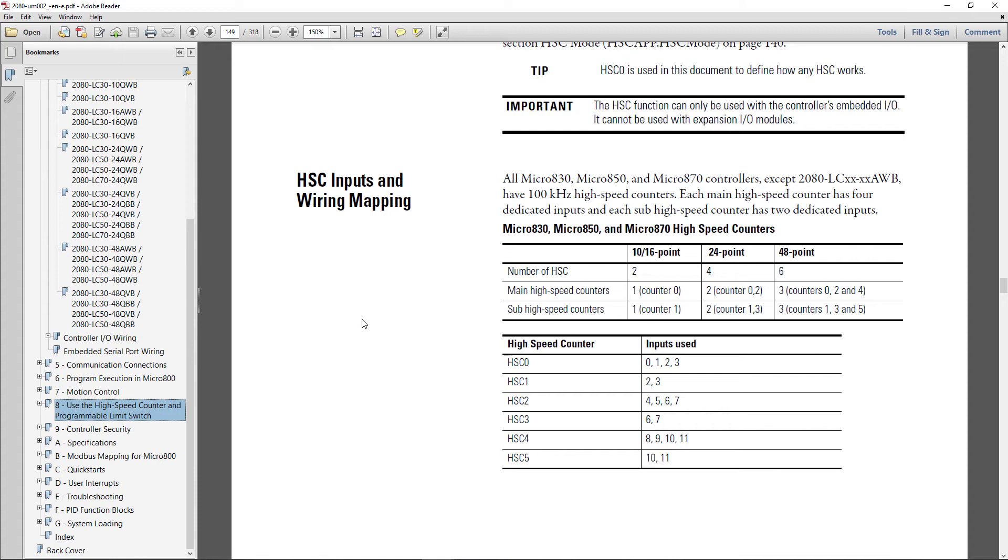But notice that between high-speed counters 0 and 1, terminals 2 and 3, inputs 2 and 3 are used. You can't use them for both. So you can't have high-speed counter 0 and high-speed counter 1.